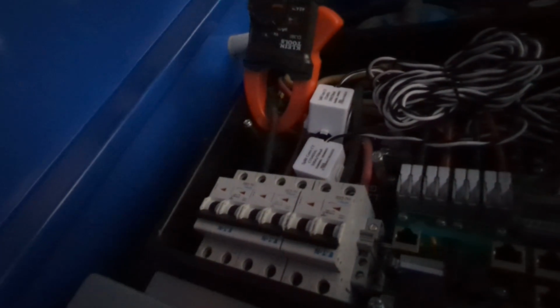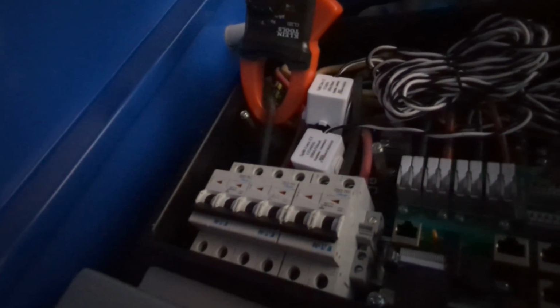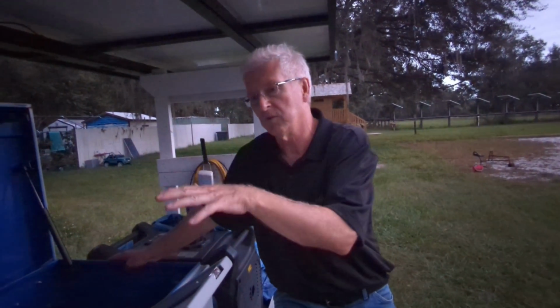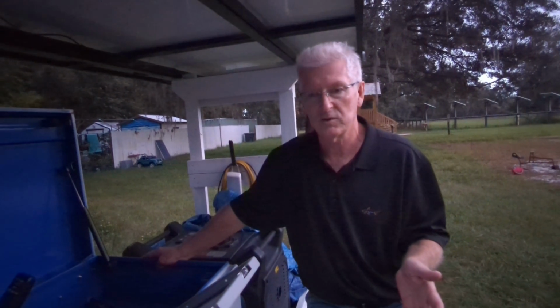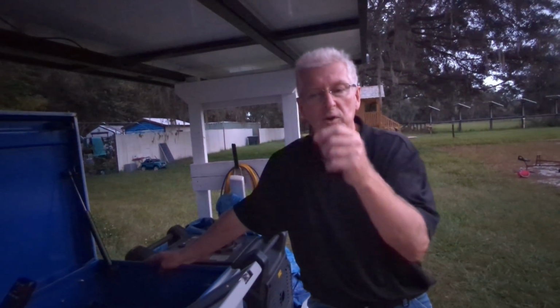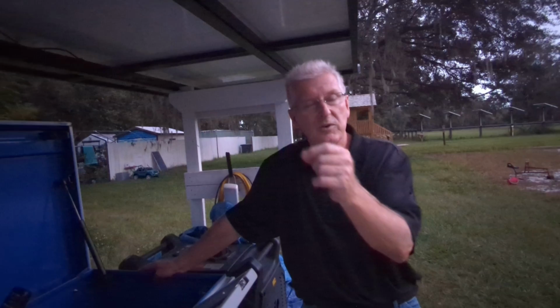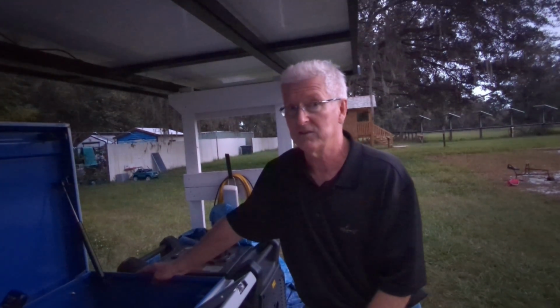That's it. And so it works because you take the red and the black here and you put it into the auto transformer, and then there's another red and black that come out of it. So you take a 120 volt circuit, you bring it into the auto transformer. You take another 120 volt circuit and you bring it into the auto transformer. The auto transformer gives you a neutral that you don't have on an individual leg. It gives you a neutral.